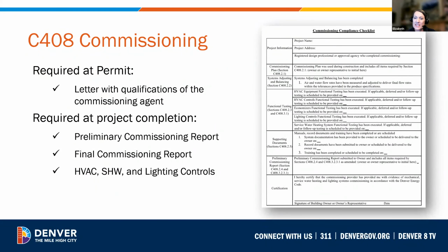The commissioning compliance checklist found in the Denver Energy Code is what documents the commissioning process. Here's a little screenshot of it on our slide here. It summarizes the results of the commissioning process for not only the HVAC systems, but also lighting and service water heating equipment. Typically, before functional testing of HVAC equipment, the test and balance contractor performs that testing and adjustment of the airflows and water flows for all major equipment to ensure that the systems are operating as indicated on the construction drawings.